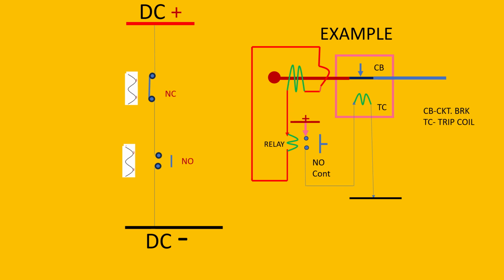I have shown these two types of contacts in the drawing, and this is shown in this way. Now I'll show you how it operates. Friends, in the picture, both the contacts' electromagnets are in de-energized condition, and in this condition one contact is closed, that is normally closed, and one contact is open, that is normally open. Now see, if I energize the normally closed contact magnet, it will open, and if I energize the normally open contact, then it will be closed. And this sequence we are using just like the binary system, 0 and 1. So see how we are doing it.